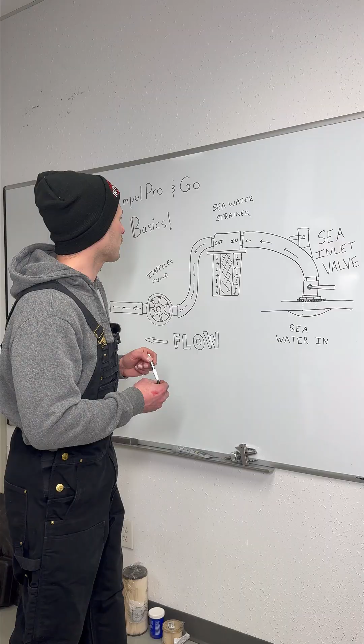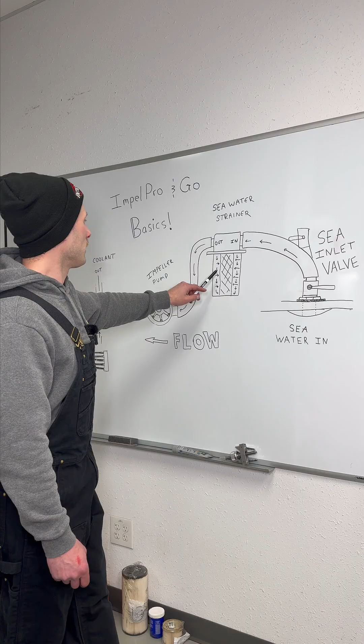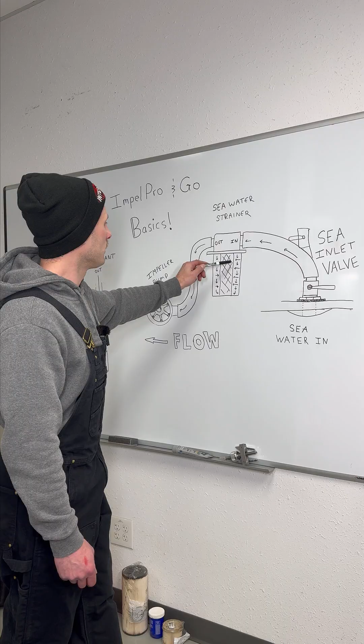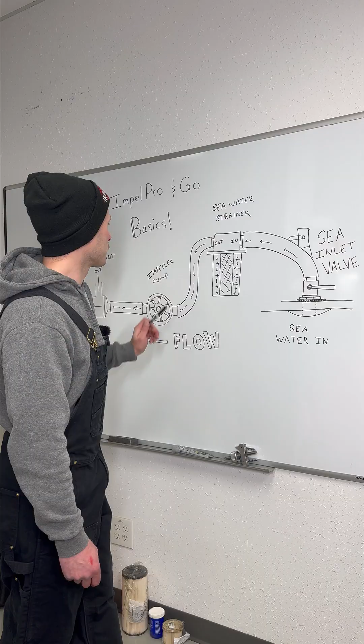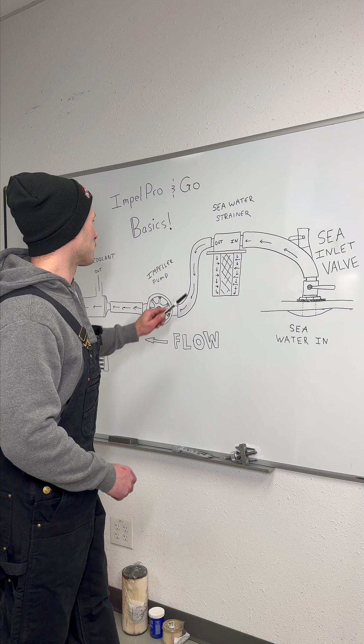From the seawater inlet, we have a strainer. With all the makes and models of strainers, yours might not look like this, but it's probably fair to say you have an inlet and an outlet, and most of the time your inlet brings water in on the outside of your filter. This gives more surface area, more room to catch seaweed, silt, mud, or shells, depending on how shallow you are. So that's our first level of protection.